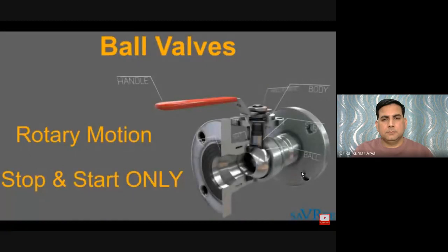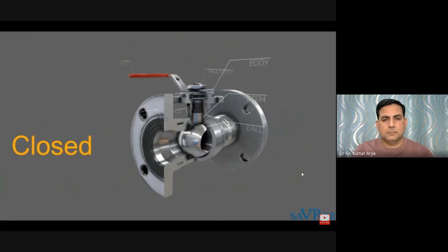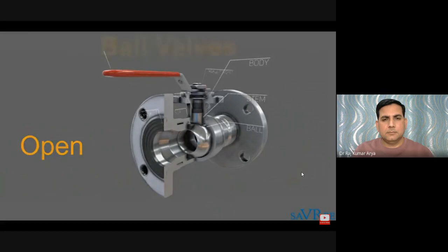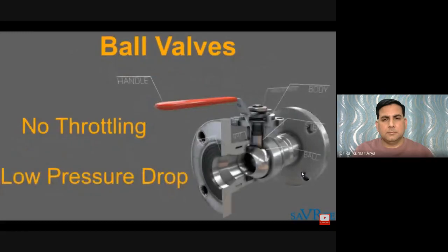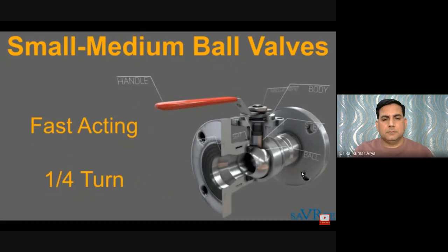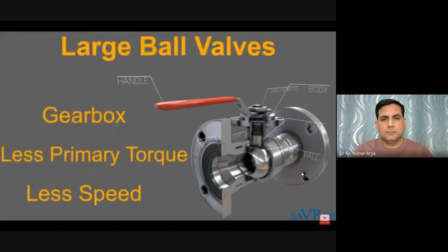A ball valve is a rotary motion valve that uses a ball-shaped disc to stop or start flow. When the handle is turned to open, the hole through the ball aligns with the valve inlet and outlet. When shut, the ball is rotated so the hole is perpendicular to the flow opening, stopping flow. Ball valves are not suitable for throttling, and the pressure drop when fully open is very low. Small to medium-sized ball valves are fast-acting quarter-turn valves, while larger ball valves employ a planetary gearbox to allow operation with a smaller hand wheel.